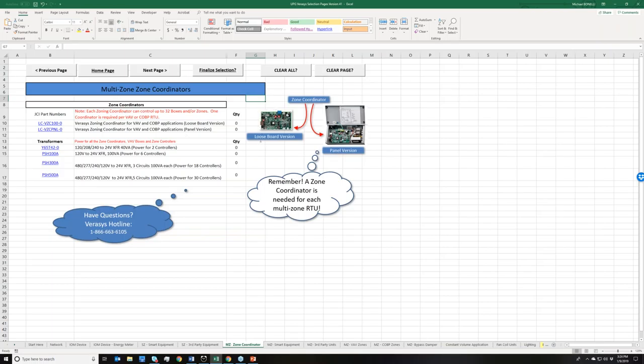It starts with this zone coordinator. Verasys requires every zoning rooftop unit to have one of these zone coordinators. All your zone dampers and all your VAV boxes will be connected to this brown terminal block, and that's what we call our zone trunk. You can only have one per zoning rooftop unit, doesn't matter if it's changeover bypass or VAV, I can only have one.